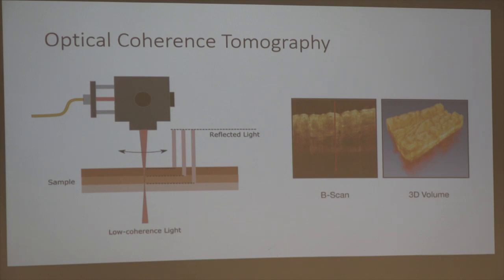So in the most simplistic form of OCT, you have a reference beam and a beam penetrating the sample. You scan your reference mirror at different depths, and only light coming from a depth that matches the path length of your reference source will interfere and give you a signal. If you move that around and scan along the sample, you can build up an intensity profile. That's the physics behind it.